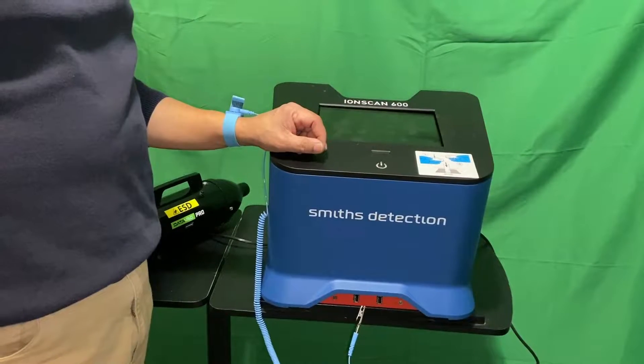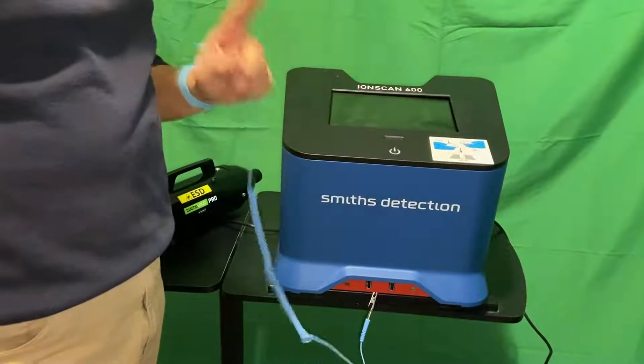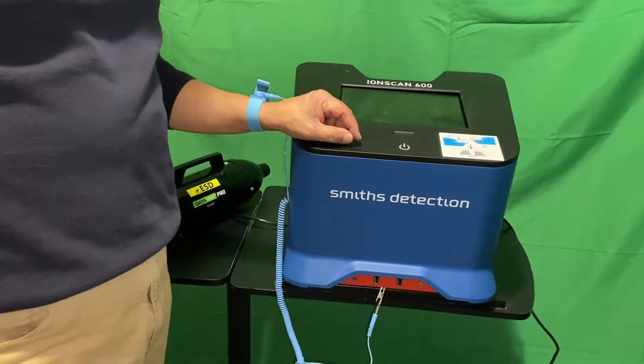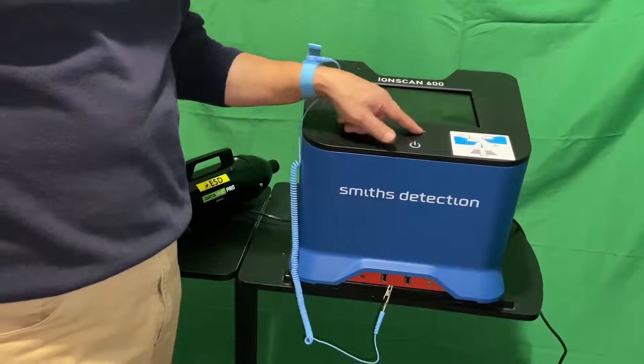Today we're going to go over how to vacuum the inlet on an IONSCAN 600. This should be done at least once a week in order to prevent dirt and dust from getting into the inlet and blocking the sensors.